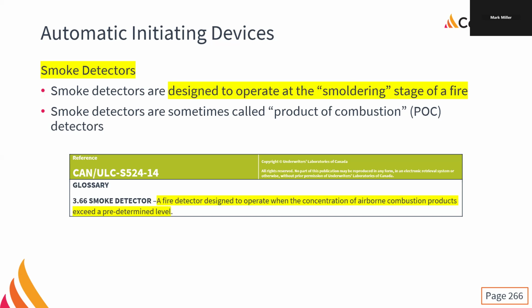So we've got our smoke detectors. Some of them are designed to operate at the smoldering stage of the fire. Some are designed to operate at the incipient stage of the fire, which is the first stage of fire. They are sometimes, and sometimes is in giant air quotes, called products of combustion detectors. No one calls them that. I'm sure someone has at some point, but no one calls them that. We call them smoke detectors. They are detecting the products of combustion, because that is what smoke is.